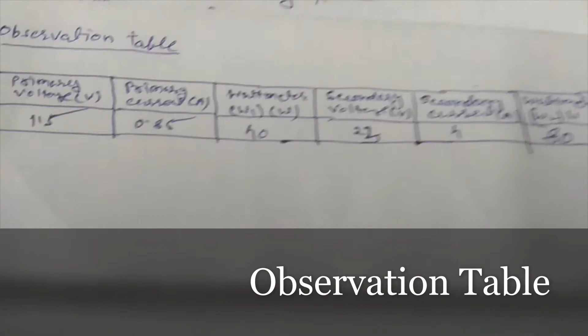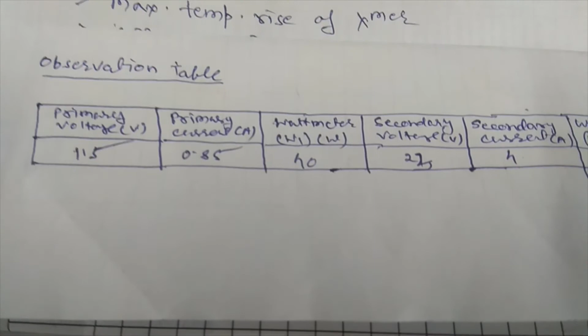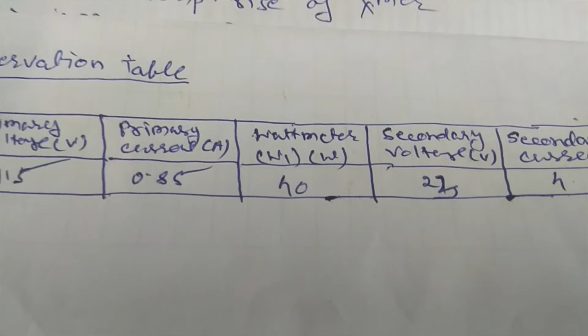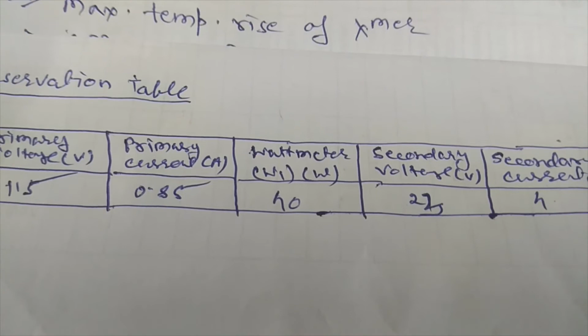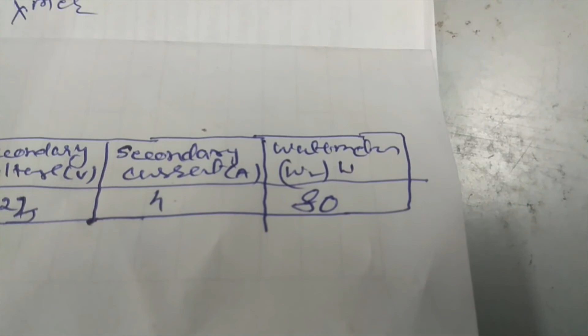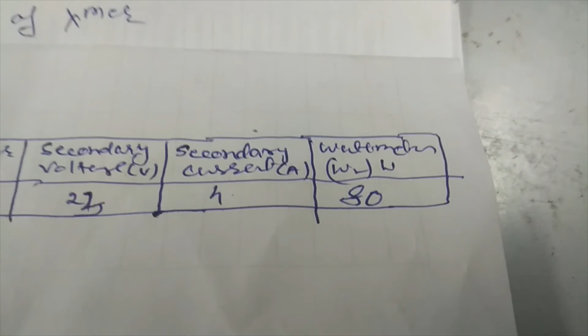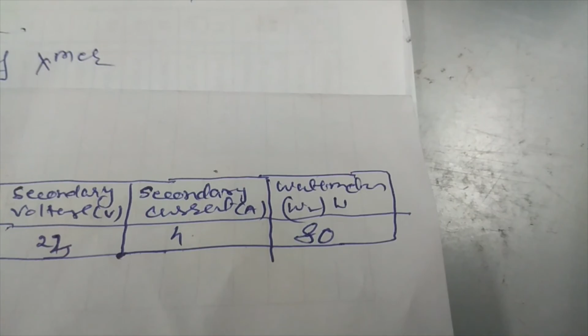Please note that the readings which we have obtained through these wattmeters indicate the losses for both of the transformers. The readings taken are now entered in this observation table. One thing we said is that the reading of the wattmeter connected to the primary side gives the core losses for both the transformers. So for each transformer we need to divide it by 2, so 20 watt would be the core losses for each transformer. Similarly, the wattmeter W2, which was connected on the secondary side, gives the ohmic losses for both the transformers, so it would be 40 watt for each transformer. Ohmic losses will be 40 watt for each transformer.